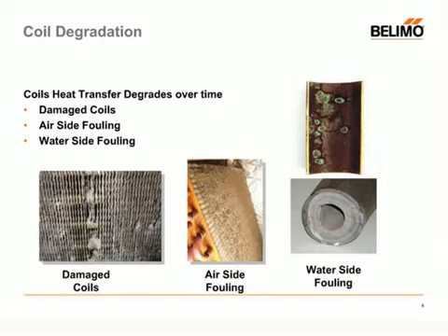Dick, is this something that you've seen commonly in talking with your customers, something that they've described as a prevalent situation? Absolutely. Most of our commercial building stock is older buildings, with air handlers that have been in place for decades. And to the extent that they do get regular maintenance, it's just something that doesn't necessarily always get done. In fact, you see more air handling units in poor condition than you see in really good condition. So this is the reality.